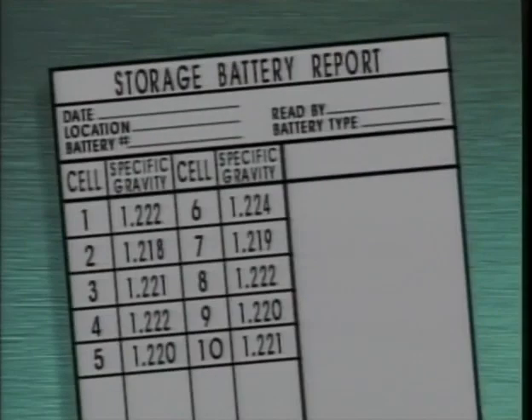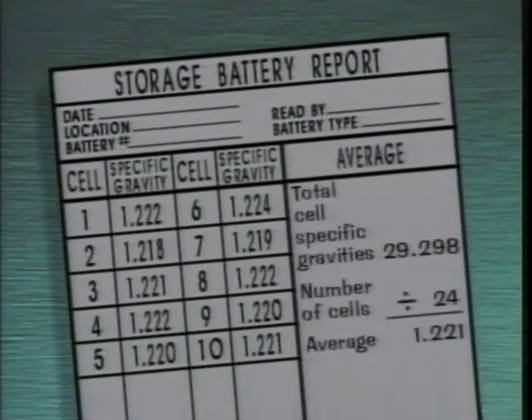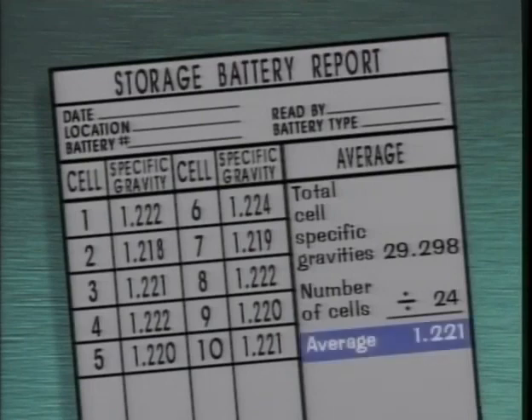Another way to evaluate cell specific gravities is to determine the average cell specific gravity. Each cell specific gravity is then compared to the average. According to IEEE Standard 450, if any cells fall below the average by .010 or more, the battery should be put on an equalizing charge.